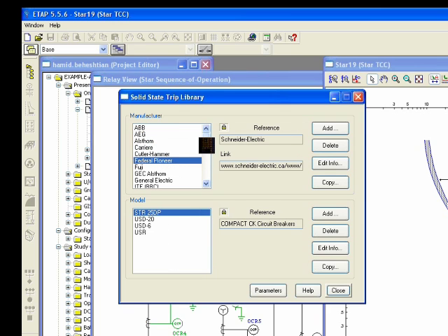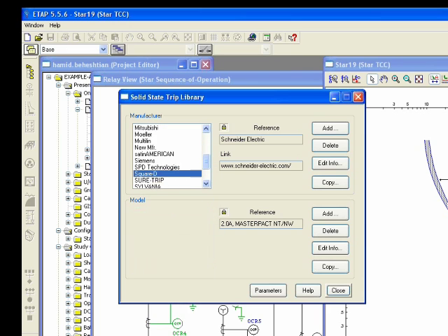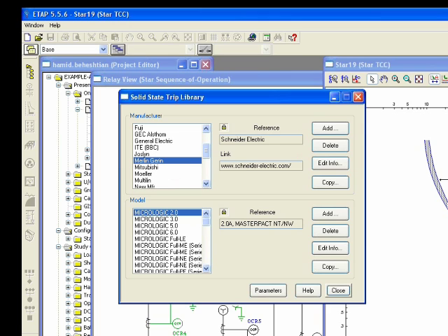One thing is very common. Sometimes clients call and say, I don't have this model under Merlin-Gerin like this one, but keep in mind some of the manufacturers are purchased or bought by a different manufacturer, or they are in a group of a big mother company like Schneider Electric in this case. So when you go to Square D, you may see the same trip device as when you go to Merlin-Gerin. Sometimes you need to be very careful about the naming of these trip devices.